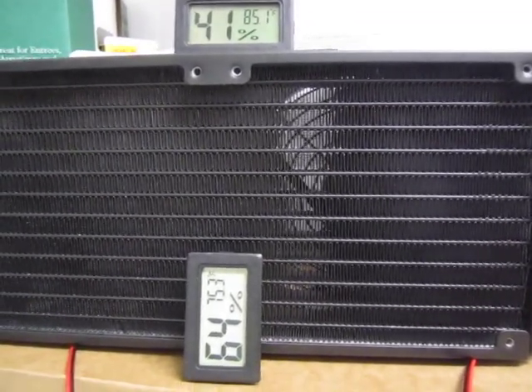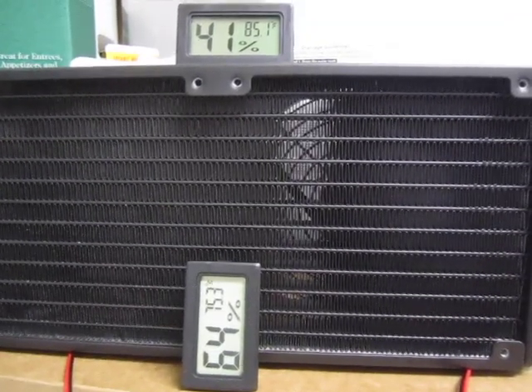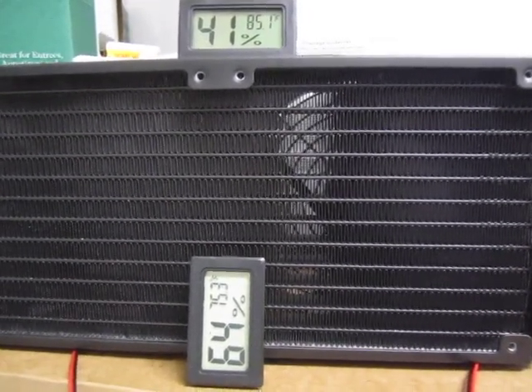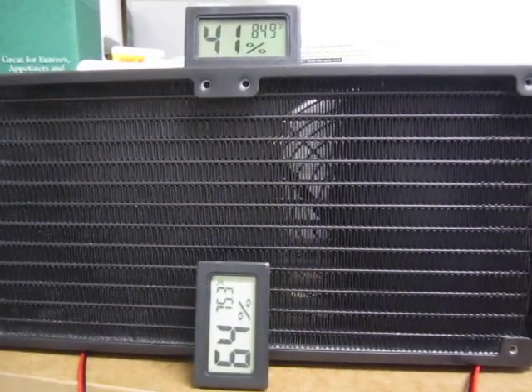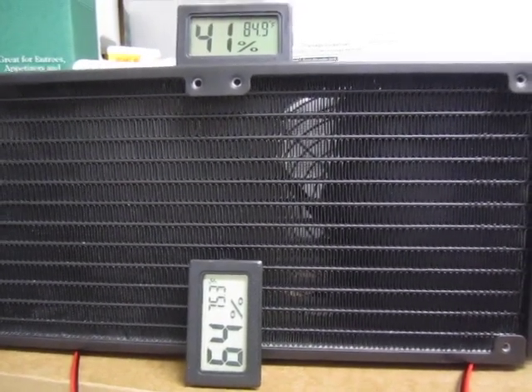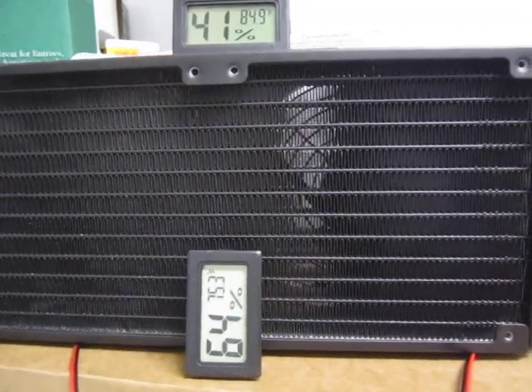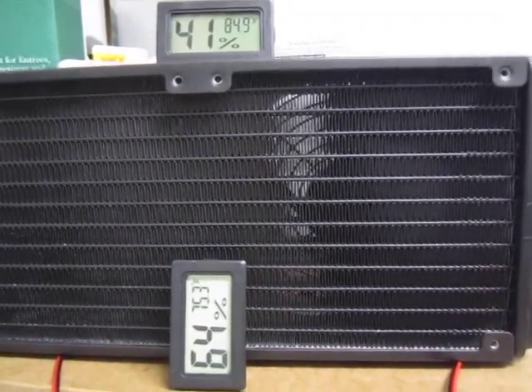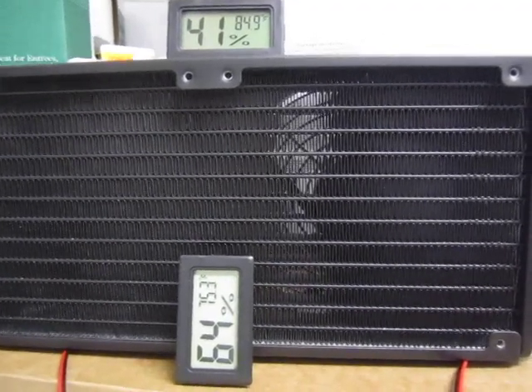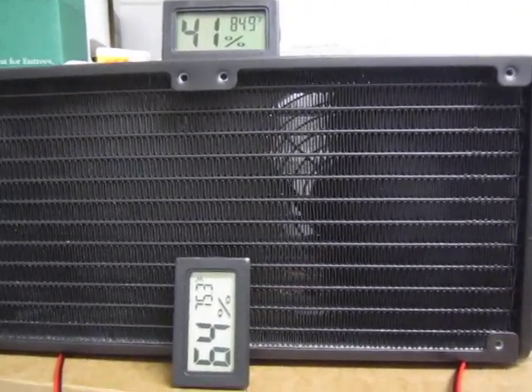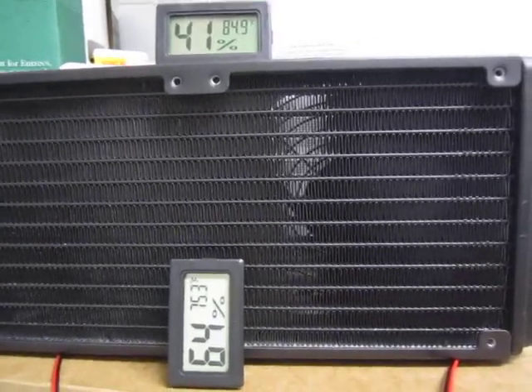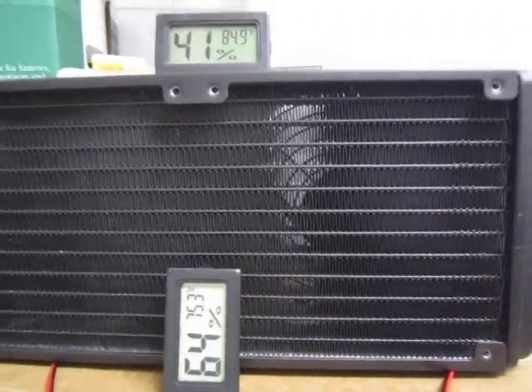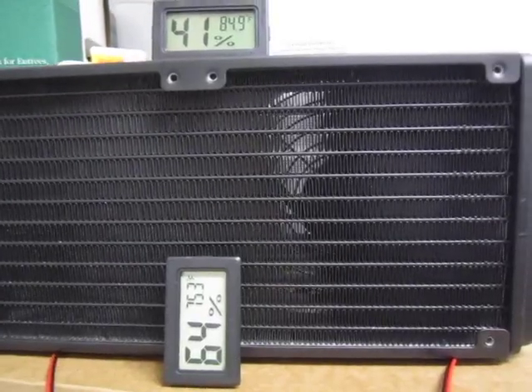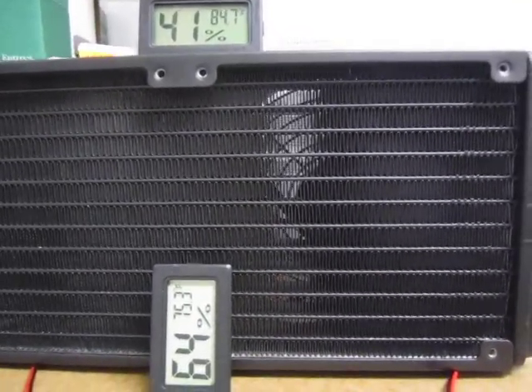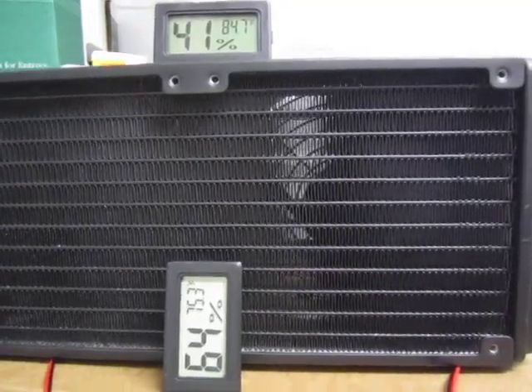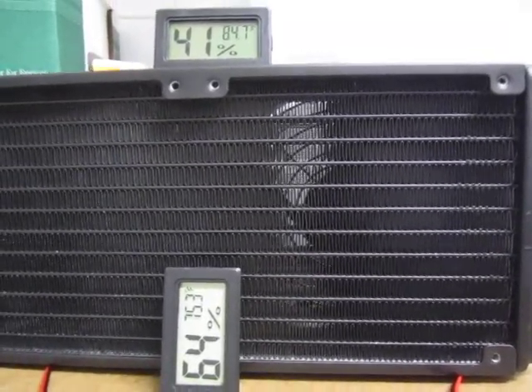Again, we expect the humidity to be larger on the cool side simply because the temperature is colder. 75.3 degrees, and I expect it's probably going to start stabilizing around 75 degrees. But this is still about 5 degrees cooler than before we turned this on. I'm not going to claim the full 10 degrees of improvement since it was only about 80 degrees at the front before we turned this on, but we still dropped the temperature about 5 degrees.